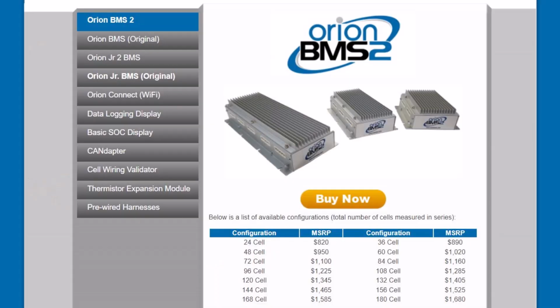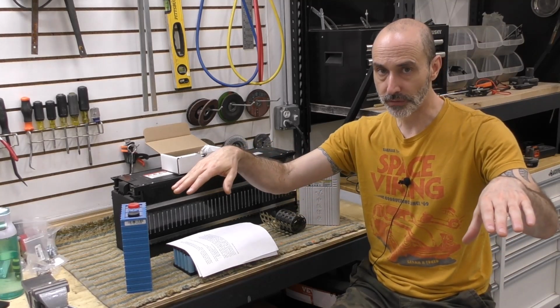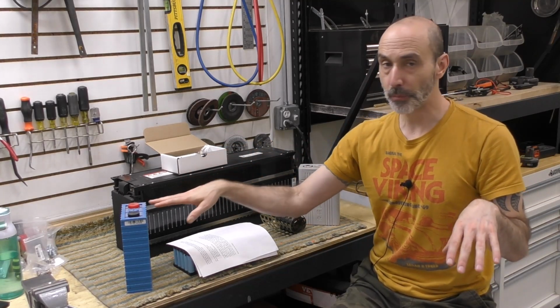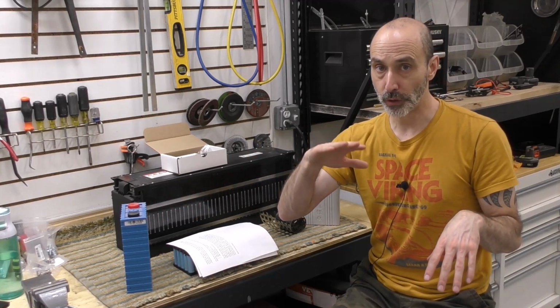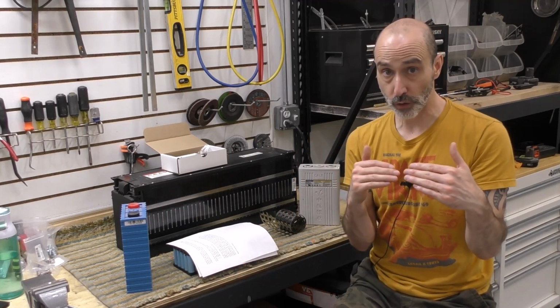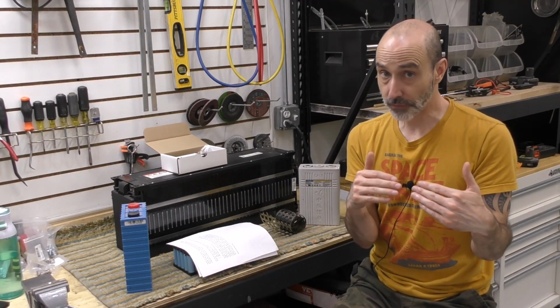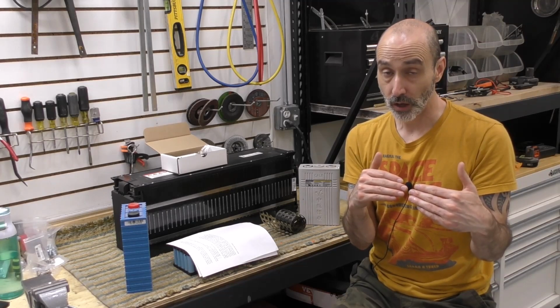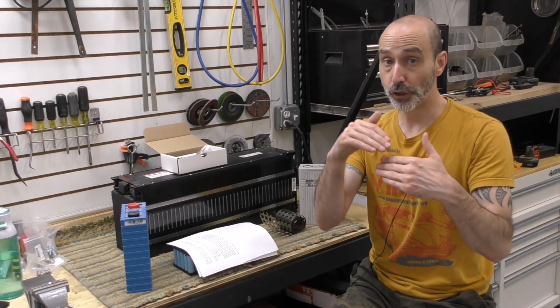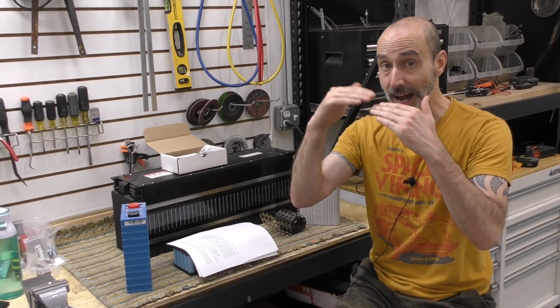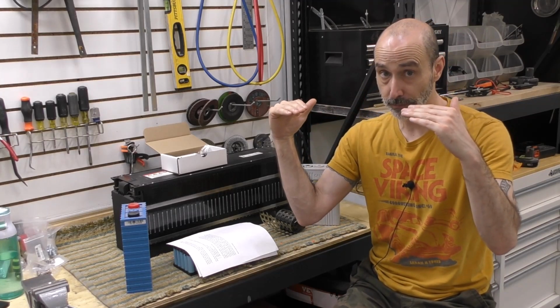A BMS is an expense, right? These can cost $1,000. The way the BMS works is you tap off the lowest level of cells, and that's what your BMS is monitoring, both for discharging, to make sure they don't go too low, or to see if there's an issue with a cell, or in charging, to shunt the voltage if it's charging faster than some of the other cells.